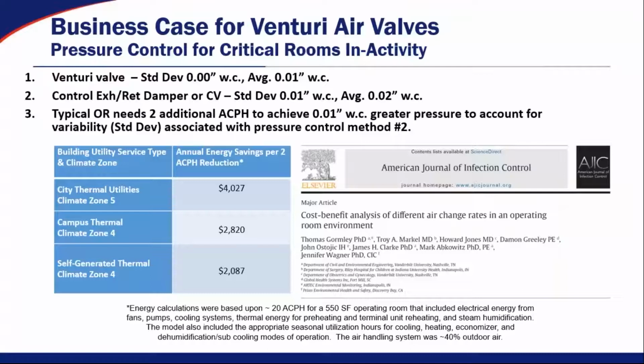And what they found was, in order to maintain the correct differential pressure across the door, you had to run the VAV boxes with 2 additional air changes per hour to achieve the differential pressure you needed and maintain that offset across the door. And if you look at that chart on the bottom of the screen, what those additional 2 air changes per hour cost is about $4,000 per year for thermal utilities for different climate control zones. And again, if you have city thermal utilities, campus thermal utilities, or self-generated, obviously the costs are going to be different. But for each individual pressurized space, you're saving at least $2,000 a year just by using Venturi valves to do the same type of airflow control. And in addition to that, we also had better infection control because we don't have that pressurization flipping across the door.